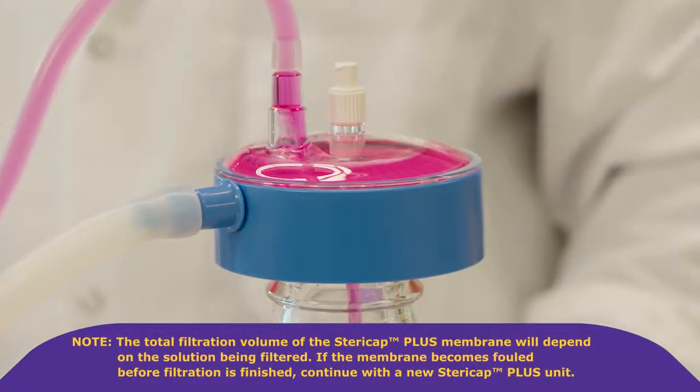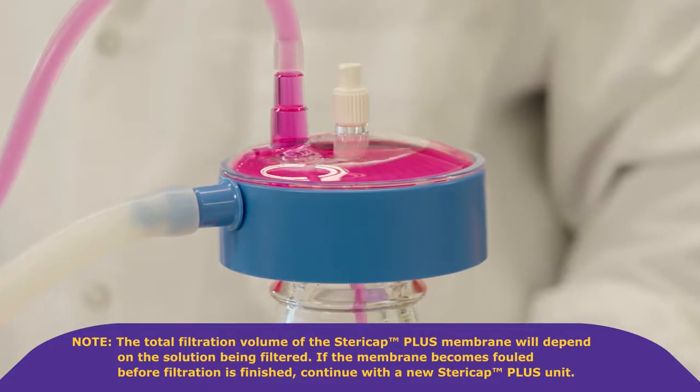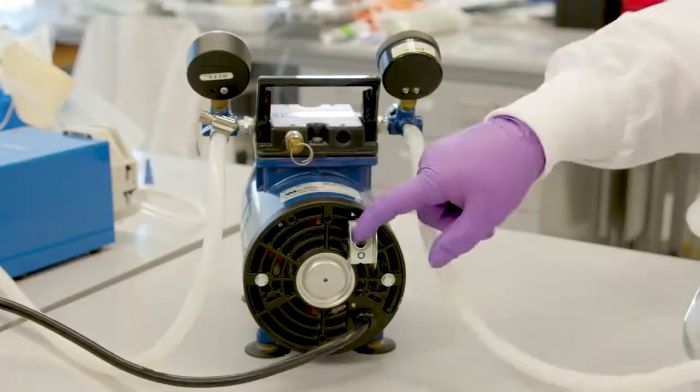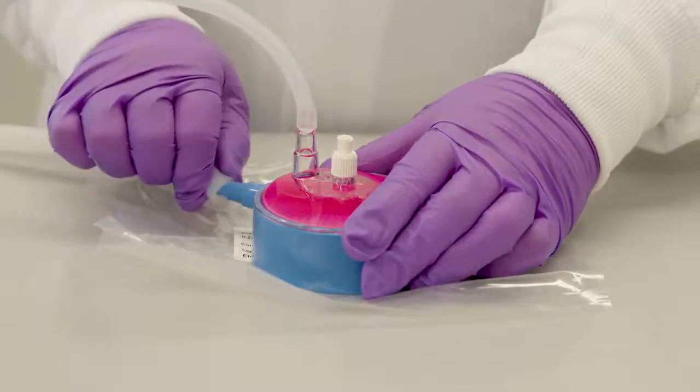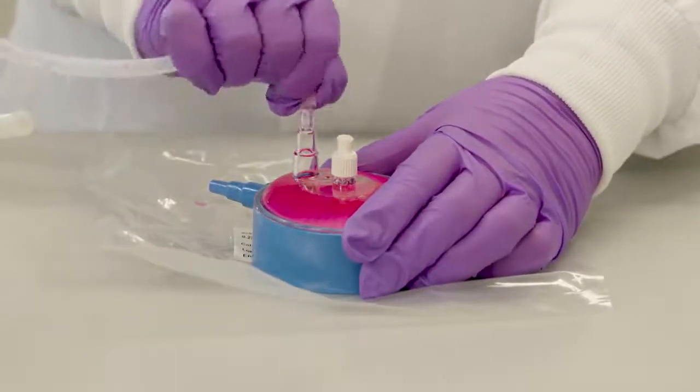Note, the total filtration volume of the SteriCap Plus membrane will depend on the solution being filtered. If the membrane becomes fouled before filtration is finished, continue with a new SteriCap Plus unit. Turn off the vacuum source to end filtration. Then disconnect the vacuum and tube set from the filter unit. Discard SteriCap Plus filter unit appropriately.